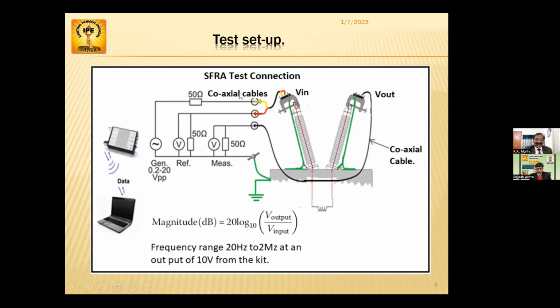The cables have to be coaxial cables. And this green lead which is seen here is actually the shortest distance you have to use. They are braided copper cables connected onto the top of the transformer, which further go to the earth as well as to the earthing point of the equipment. The frequency range is 20 Hertz to 2 megahertz at an output of 10 volts from the kit.